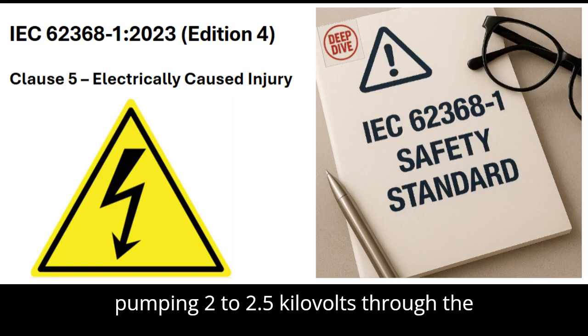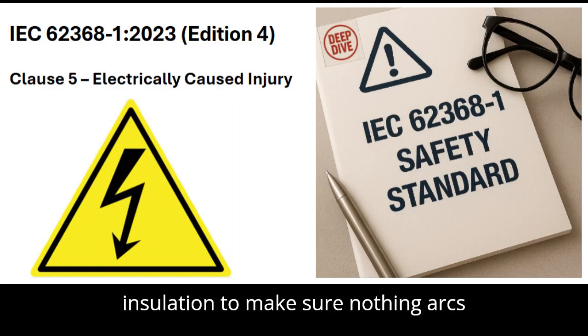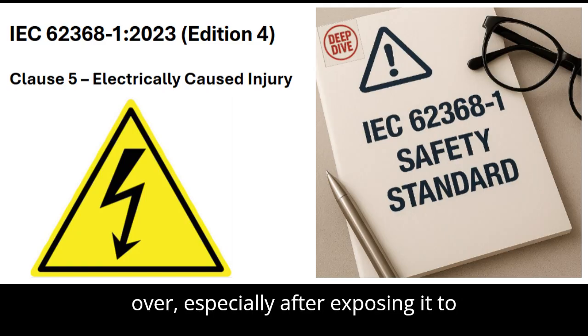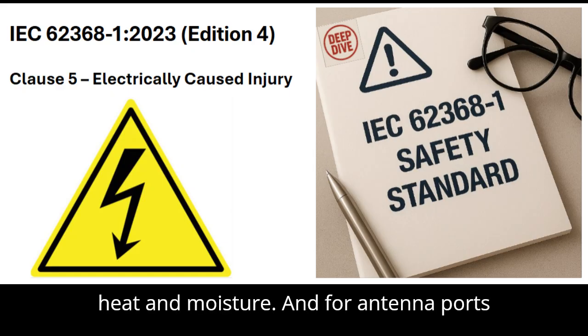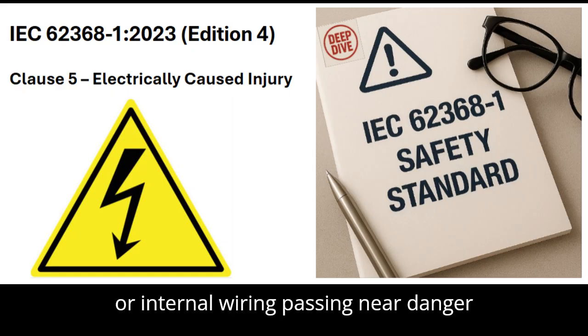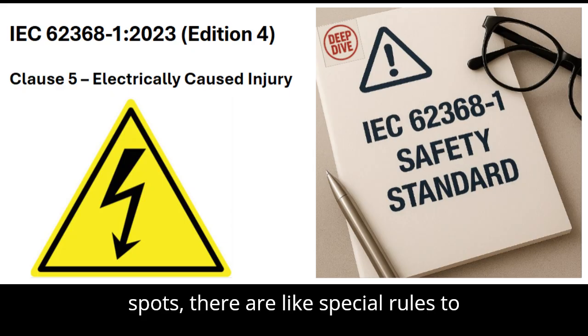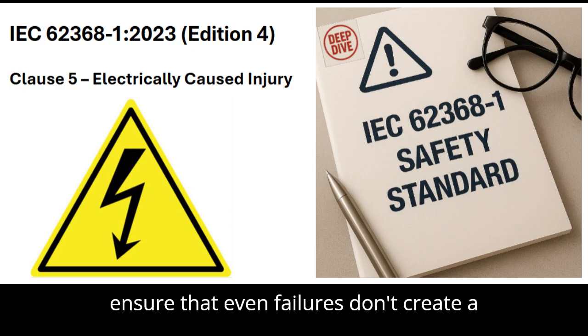pumping 2 to 2.5 kilovolts through the insulation to make sure nothing arcs over, especially after exposing it to heat and moisture. And for antenna ports or internal wiring passing near danger spots, there are special rules to ensure that even failures don't create a shock pathway.